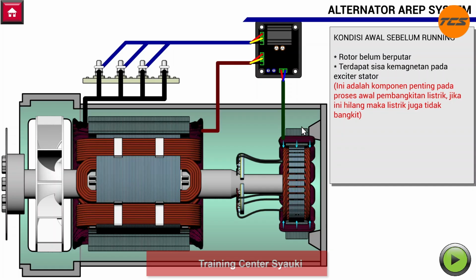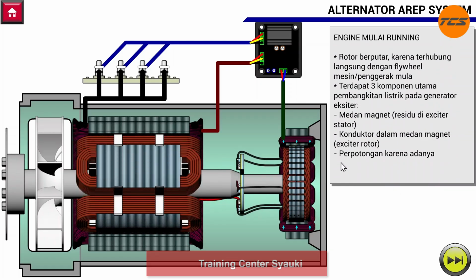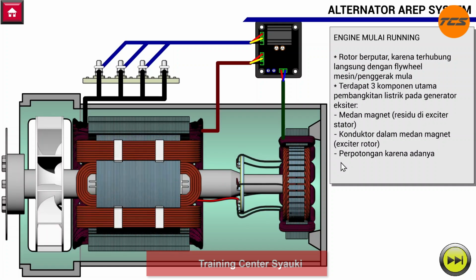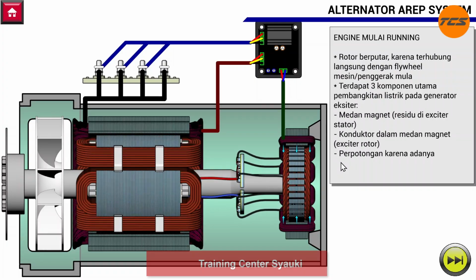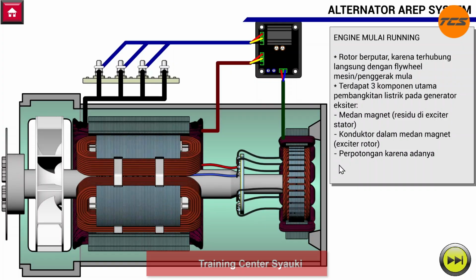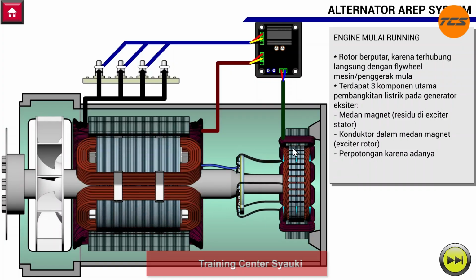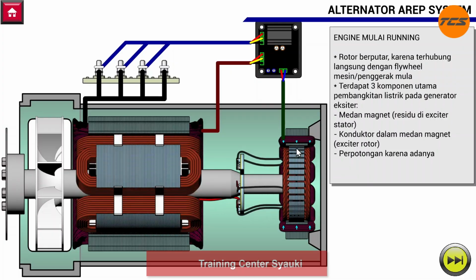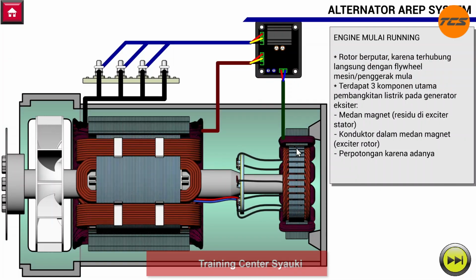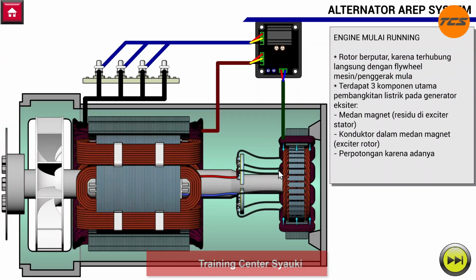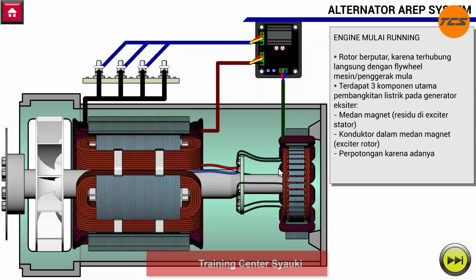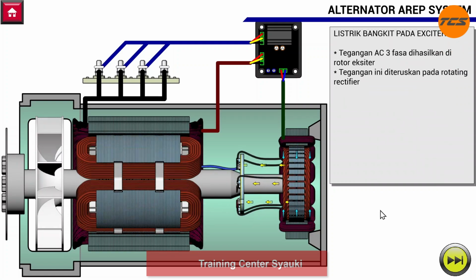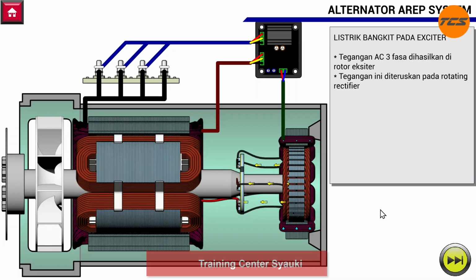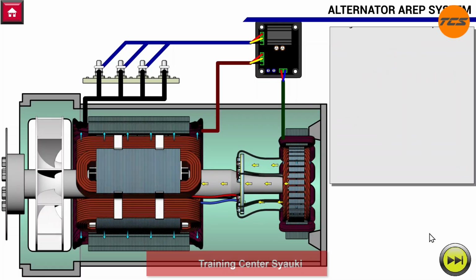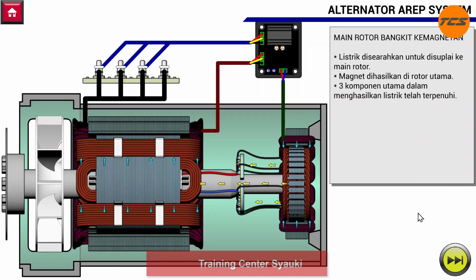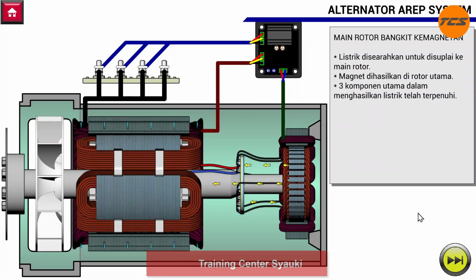When the engine starts running, like this, the rotor begins to rotate. There are three essential elements required for electricity generation. First is the magnetic field from residual magnetism. Number two is the conductor in the exciter rotor. Number three is relative motion between the conductor and the magnetic field, because the rotor is rotating. As the rotor rotates, three-phase AC voltage is generated in the exciter rotor. This voltage flows into the rotating rectifier where it is converted into DC voltage. This DC voltage is then supplied to the main rotor, creating a magnetic field in the main rotor.